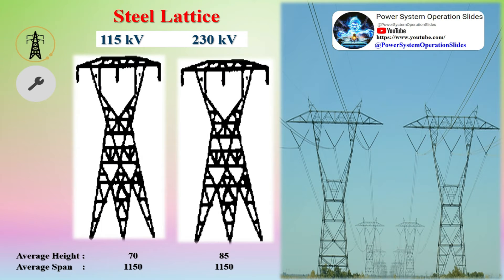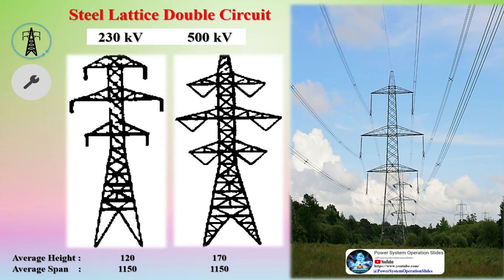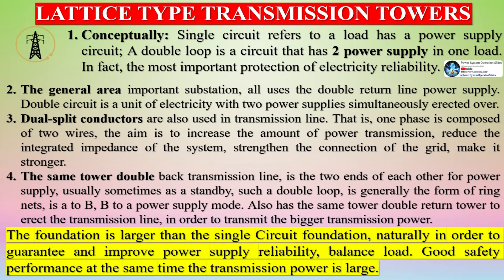A lattice tower is a framework construction made of steel or aluminum sections, and is the most common type for high-voltage transmission lines. Aluminum is used for reducing weight, such as in mountainous areas where structures are placed by helicopter, with the extra material cost offset by lower installation cost. Lattice steel towers are generally made of angle-profiled steel beams (L or T-beams), and trusses are often used for very tall towers.